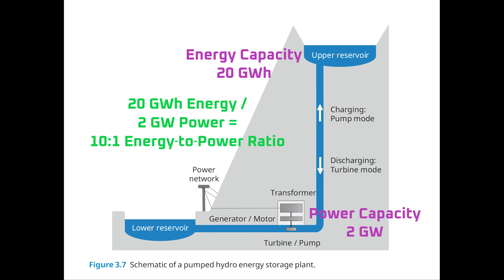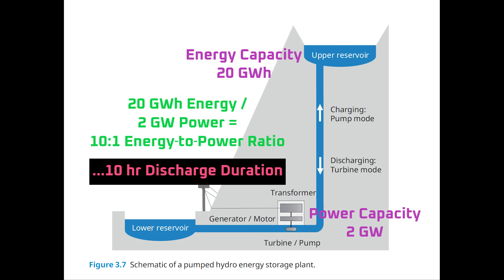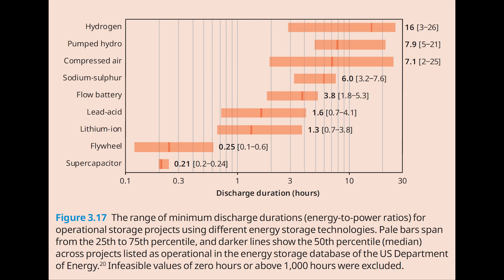The 10-to-1 energy-to-power ratio means that a large pumped hydro station can provide power for about 10 hours, which is called discharge duration. Discharge duration is generally abbreviated to just duration in grid storage products. Now that we know the technical definition of duration, we can look at why it's so tightly tied to the economics of grid storage. In short, it's because each technology has strengths and weaknesses for converting energy to power that's dictated by physics and engineering, and that in turn results in a duration where each technology is most cost efficient.